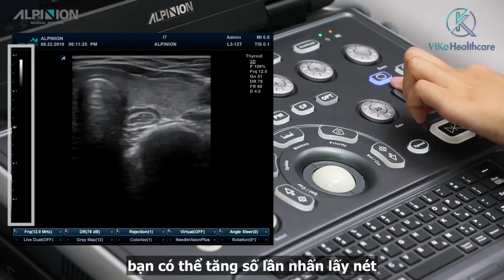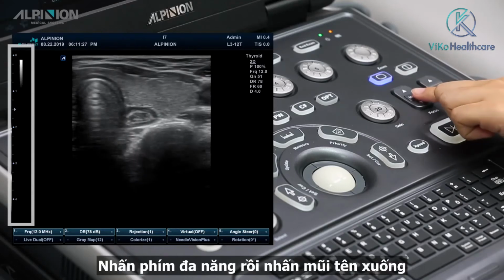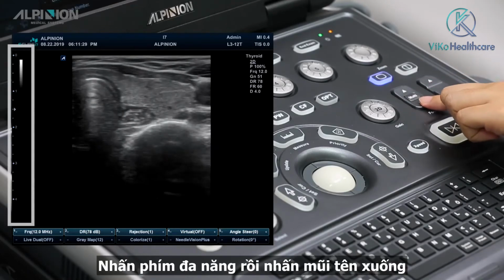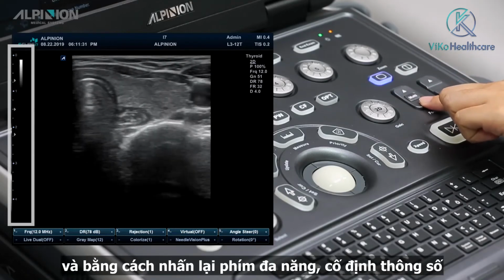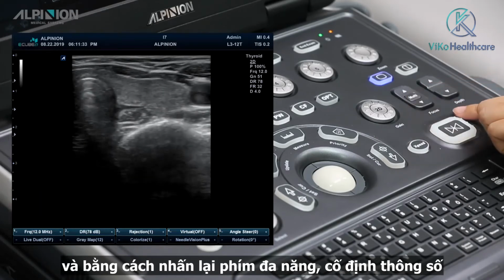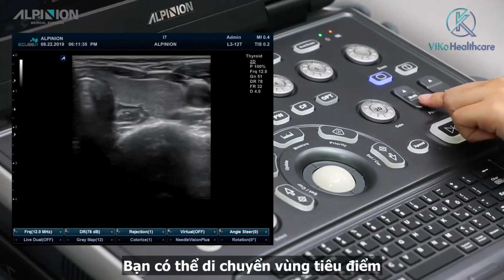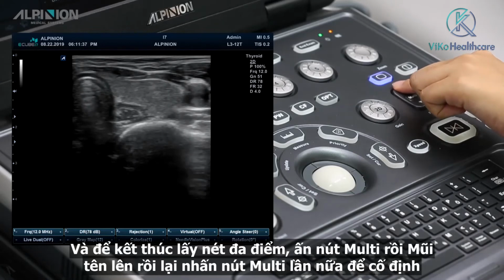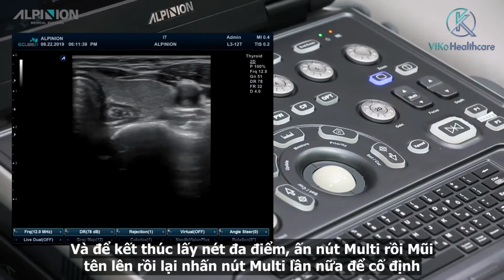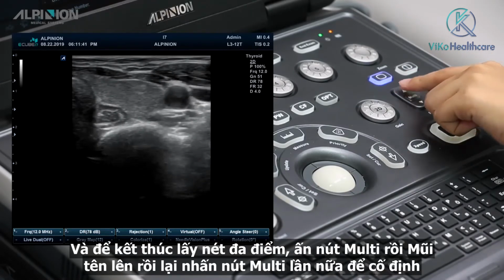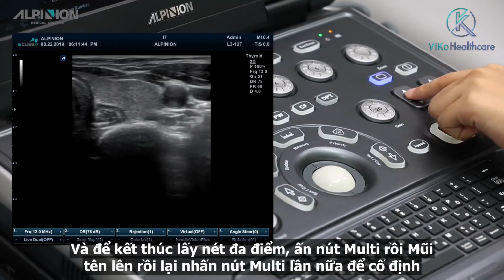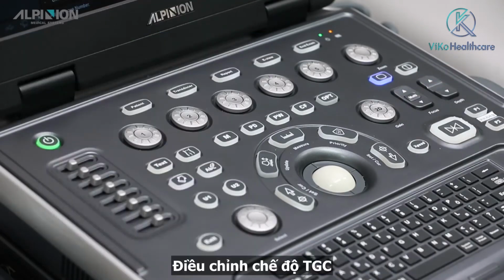Also, you can increase the number of focus. Press the multi-key, then press the down arrow, and by pressing the multi-key again, fix the number. You can move the focal zone again. And to finish multi-focus, press multi and press the up arrow, and press multi again to fix it. Adjust TGC slide controls.